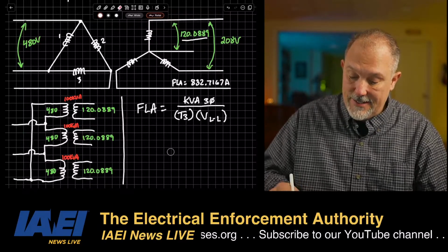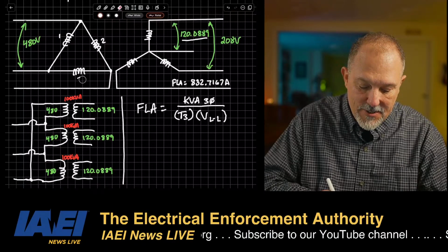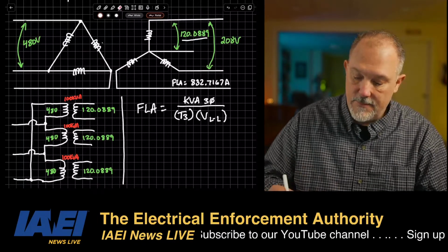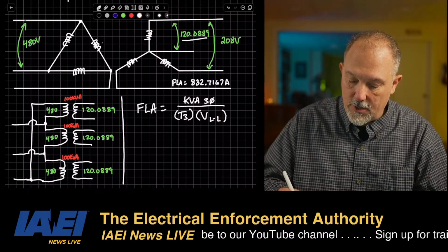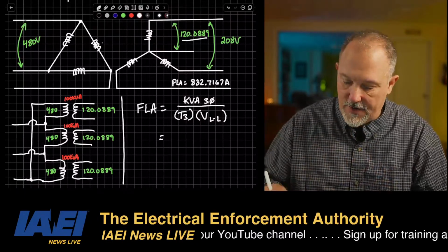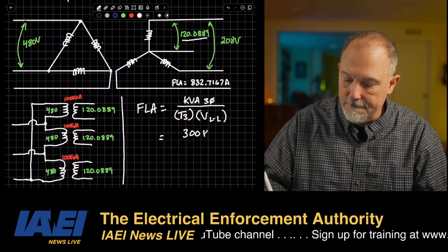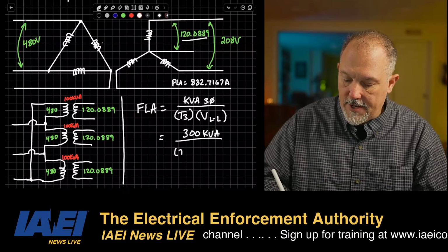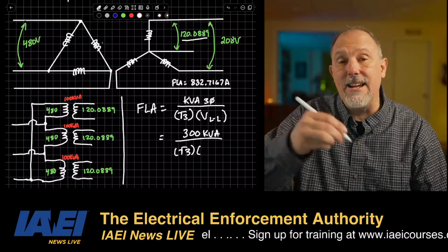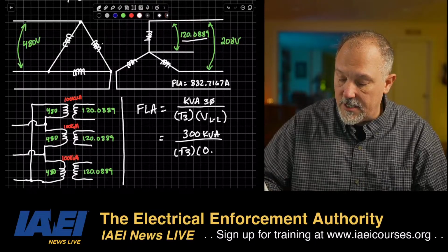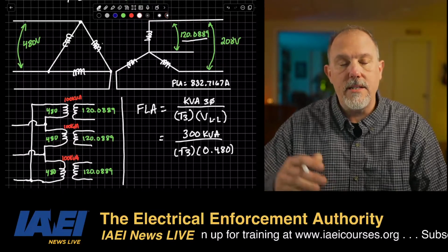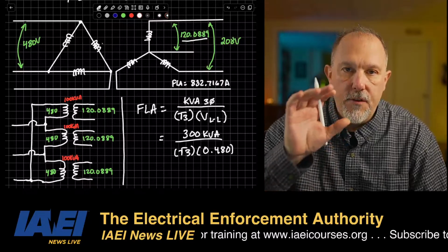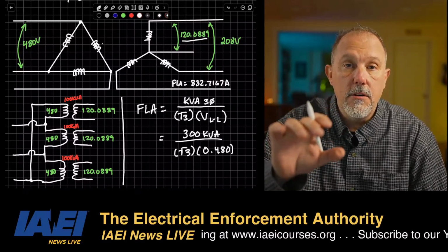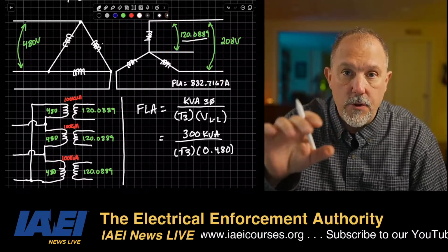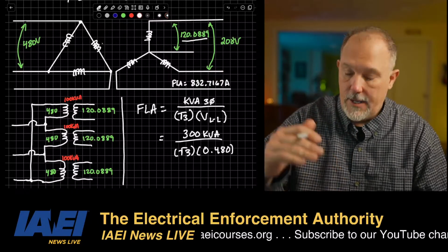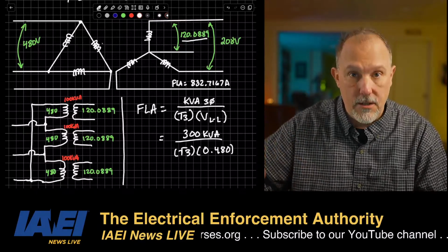Now, here's what I am going to do. I'm going to calculate my primary full load amps, and we're going to write it up there, and then we'll do the reflection and verify. So I have 300 kVA divided by the square root of 3 divided by the line-to-line voltage on the primary, which is kV 0.480. Why is it 0.480? Because voltage is 480 volts. Kilovolts is 480 volts divided by 1,000. And that's why it's 0.480 kilovolts.